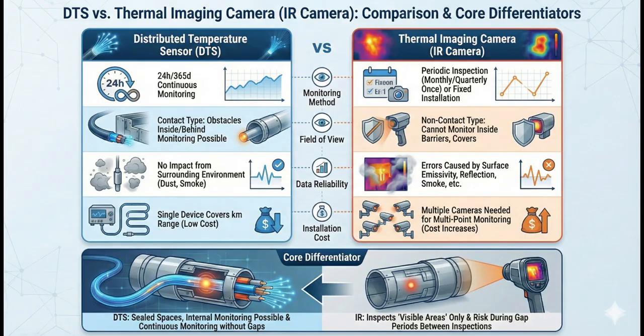Compared with thermal cameras, thermography typically checks only visible areas on a periodic basis. It has limitations inside switchgear or in hidden sections, and anomalies may be missed during the gap between inspections. DTS eliminates those gaps with 24/7 continuous monitoring, and directly measures areas that thermal cameras struggle to see, such as inside cable trays or enclosed structures. From a preventive perspective, DTS enables more consistent data-driven operations.